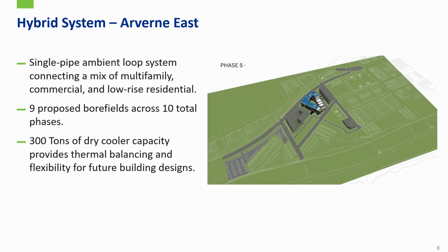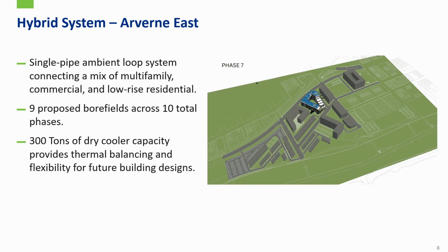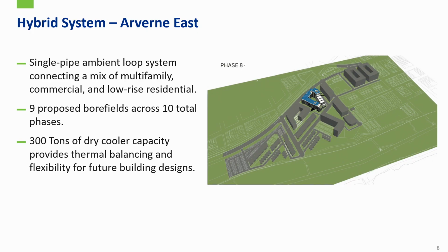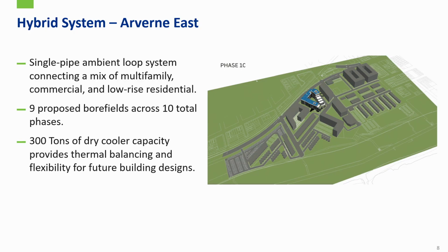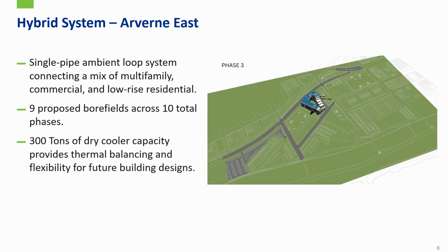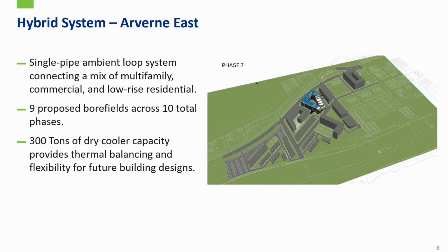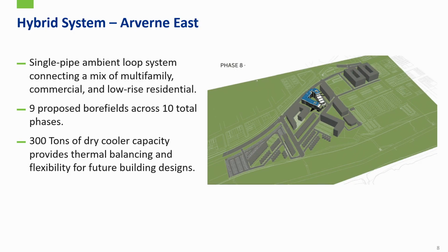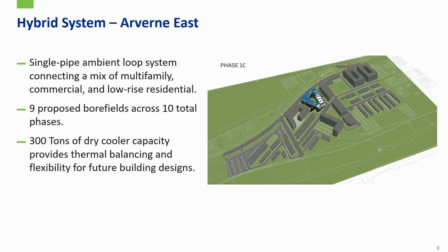Because of the size of these buildings, it's a very cooling dominant system. Spaced out through the phases, we have 300 tons of dry cooler capacity. Since it's a thermal energy network, we already need to measure the BTUs anyway, so we'll know our net imbalance of heating and cooling. Over the course of the year, these dry coolers run an adjustable number of hours, and that's used to keep our bore fields from overheating. They're just one way in this case.